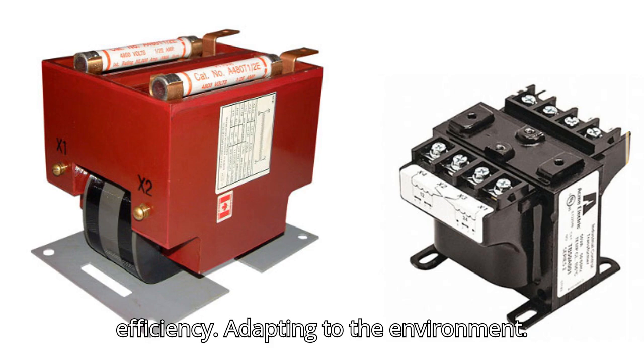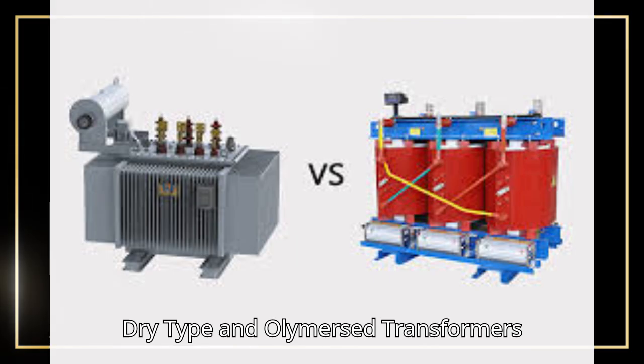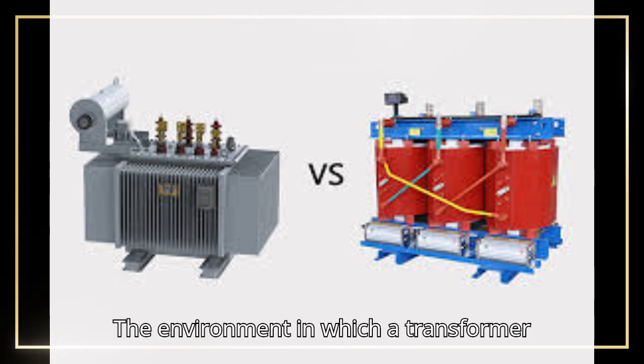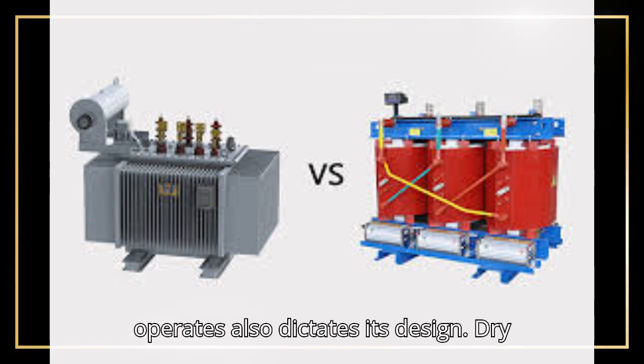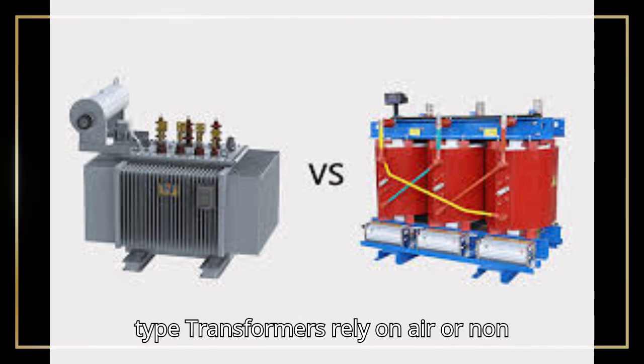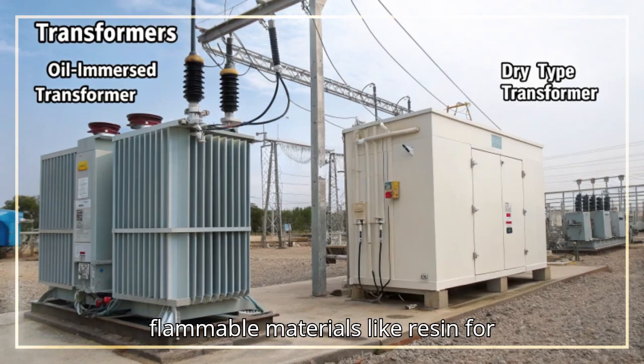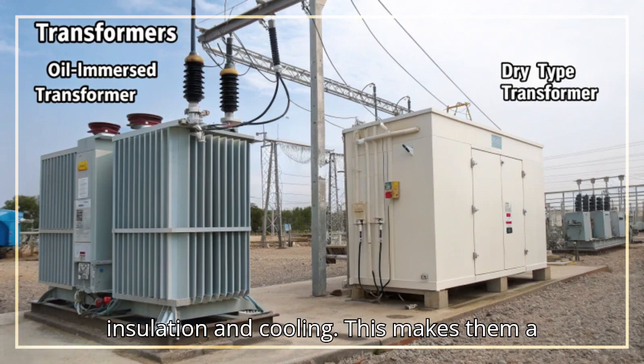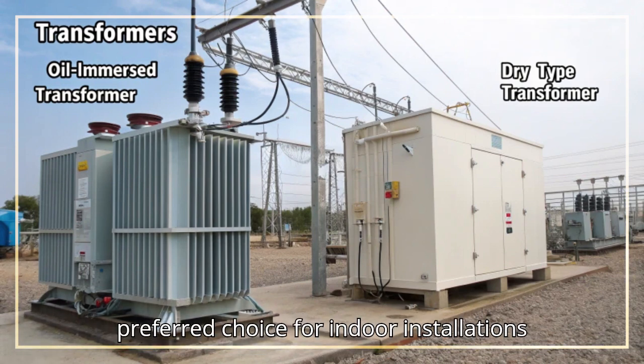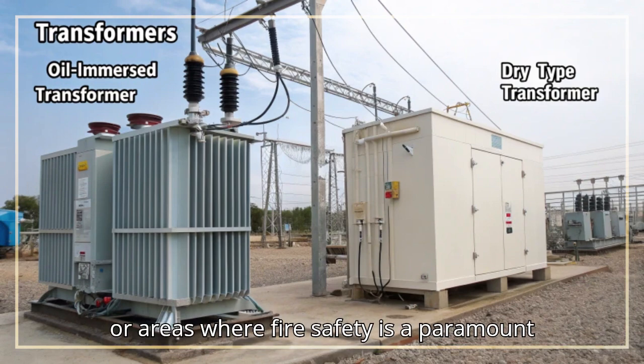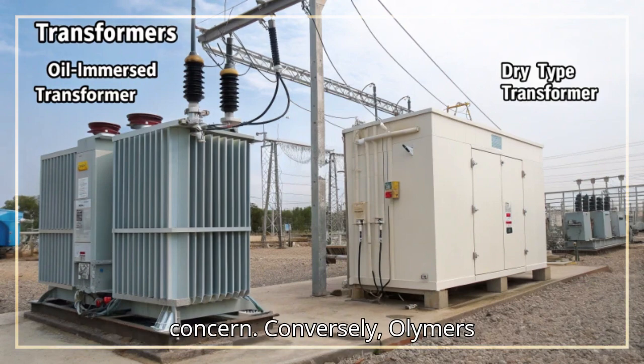Adapting to the environment: dry-type and oil-immersed transformers. The environment in which a transformer operates also dictates its design. Dry-type transformers rely on air or non-flammable materials like resin for insulation and cooling. This makes them a preferred choice for indoor installations or areas where fire safety is a paramount concern.